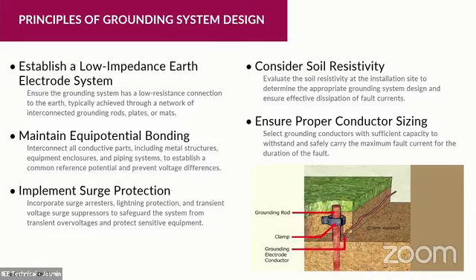Second, part of the principle is that we maintain equipotential bonding. Equipotential bonding, as we know, is the interconnection of conductive parts, including metal structures, equipment enclosures, and piping systems, establishing a common reference potential to prevent voltage differences. This is very critical when it comes to a certain fault that may happen in our system.